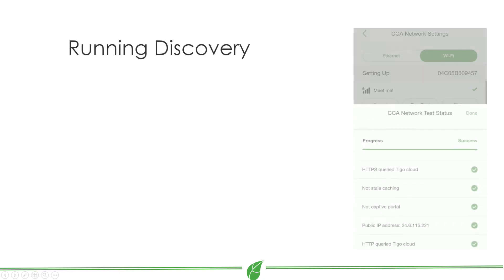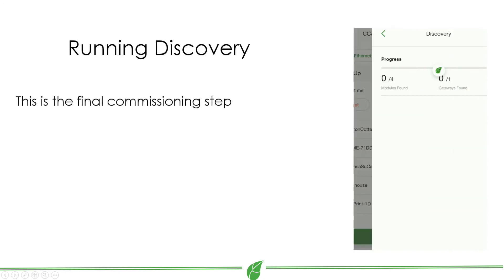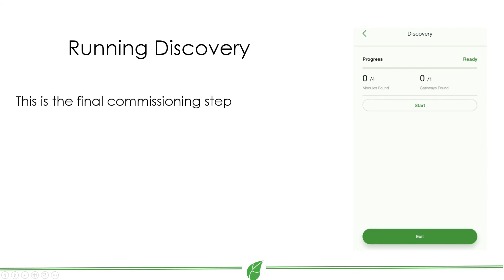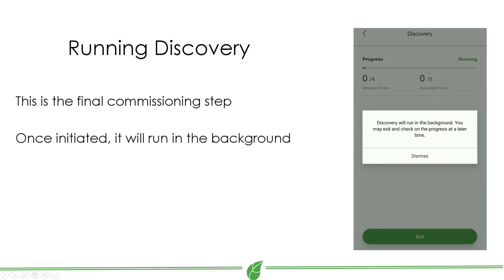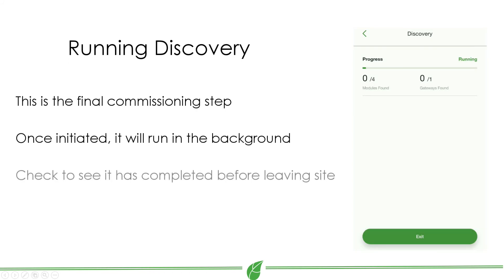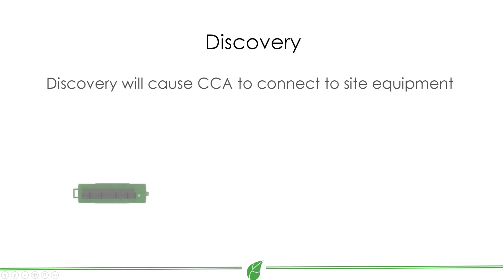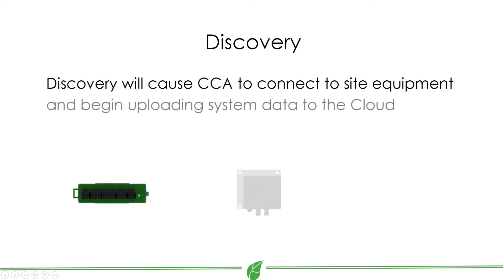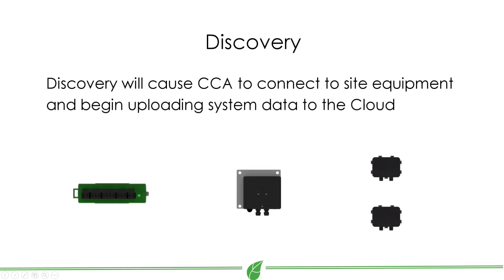The last step of the commissioning process is called discovery. Initiate discovery and it will run in the background. Feel free to leave the app or disconnect your phone from the CCA and reconnect later before leaving the installation site to check its progress. During discovery, your CCA is connecting to site equipment and verifying that all installed modules are communicating with it successfully.